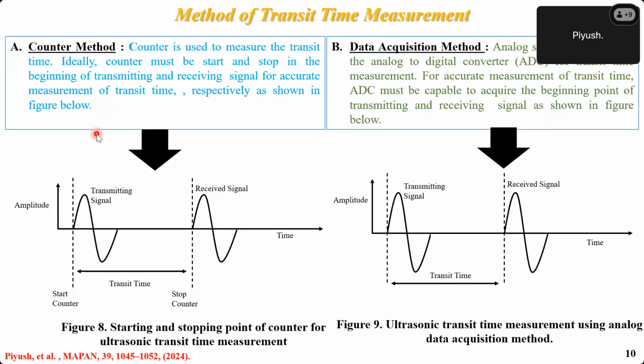In the counter method, as shown in figure 8, a timer is started at the beginning of the transmitting signal, and it stops at the beginning of the receiving signal. In the data acquisition method, the entire signal, the transmitting signal and the receiving signal, is acquired with the help of an analog to digital converter, and by analyzing it, we can measure the transit time.